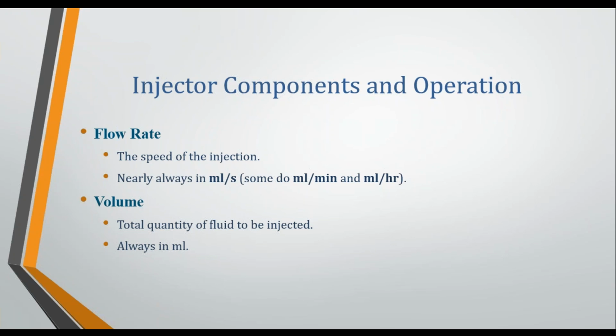So the flow rate is the speed of the injection, how fast we're going to fire fluid into the patient, regardless of how much. Now, the volume is the total quantity of fluid that we're going to inject in the patient, regardless of the speed. And the volume is always programmed in milliliters.